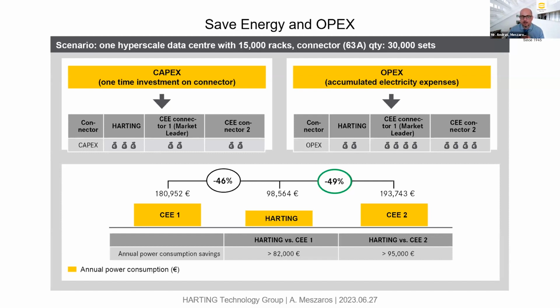We wanted to calculate what that would mean. If we take a bigger hyperscale, or something between hyperscale and a normal size data center, let's say 15,000 racks. If we take a 63 ampere connector as an example, with 2 connectors per rack, that's 30,000 connector sets.